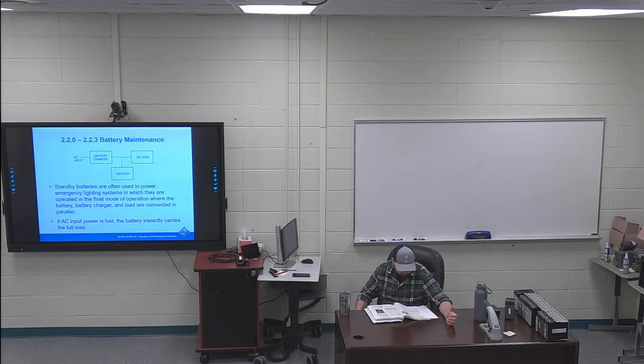Paragraph in the bottom left of page 12, first sentence is highlighted. The method of determining battery capacity is by performing a load test. Load test. To measure the amount of power a fully charged battery is capable of delivering over a specific period of time. Specific time period. But they do a load test to determine battery capacity. Simple enough.